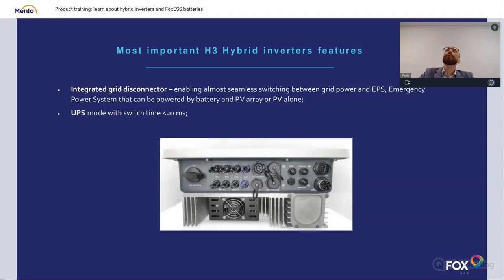But if you have some simple installation, you can connect grid directly to the inverter, get your power directly from the EPS, and give it to the client grid, to the consumer unit. And if you do such a thing, you are using this integrated disconnector, and when the blackout strikes, this grid terminal will be galvanically isolated, and this EPS output will still provide power without even interrupting the power flow. It will only disconnect from the grid. You won't notice because of the UPS switching time.